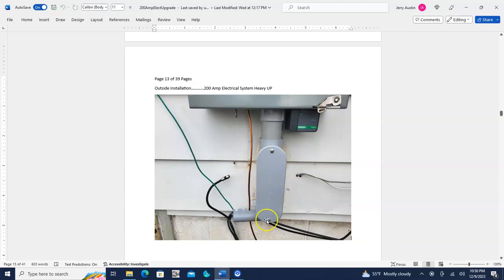These covers are on this because there's some big wires that go through this thing, so you need this room in here to be able to bend those wires and put them on through there. This is a little holder here for the ground rod wire that goes down to the ground rod. It hooks into one, and then from there it goes over and hooks into the other one. They are 6 feet apart, and this ground wire cannot be in different sections. It's got to be all one solid piece. It can't be spliced together.